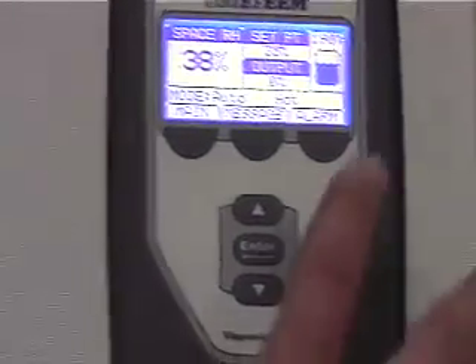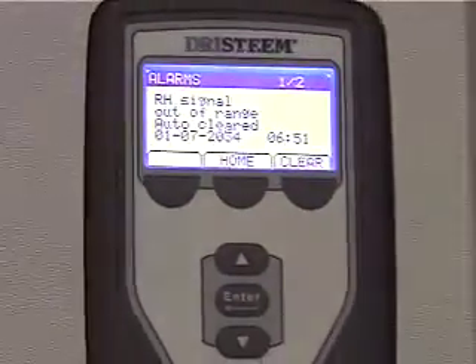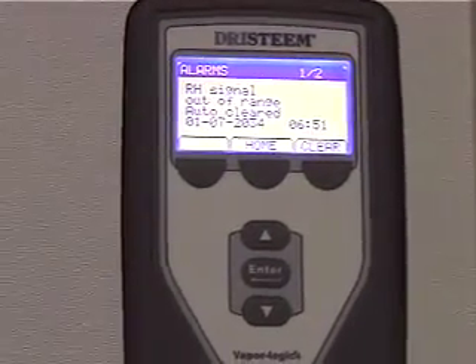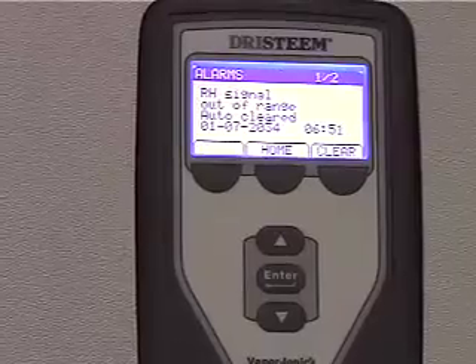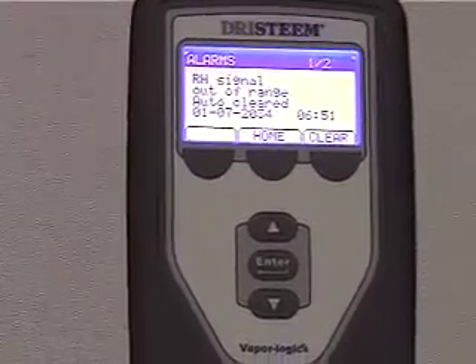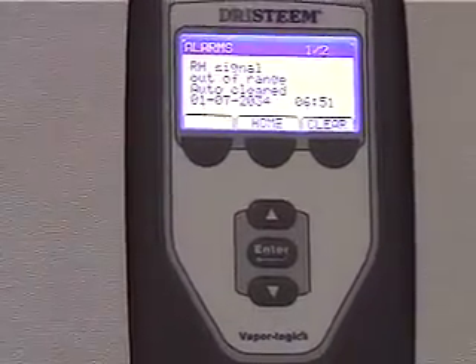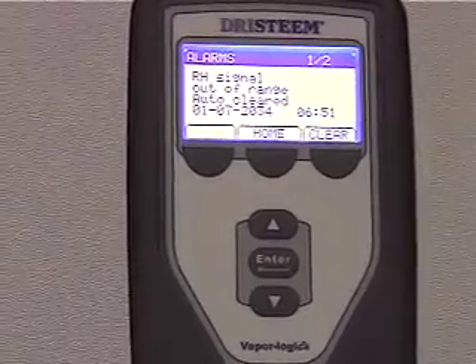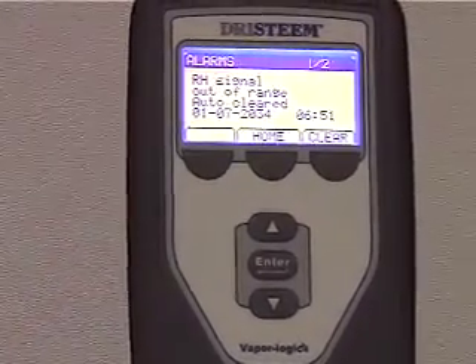We're over set point. Now in here, one of the things we can do, you've got your main, your message, your alarms. You come in here to your alarms. It says it had an alarm clear back. I think our date's a little off. So it said that the signal it was being given was out of range, which definitely tells us that somebody's doing something here.